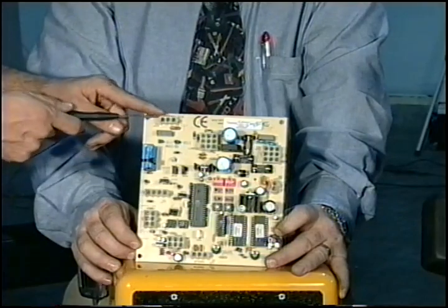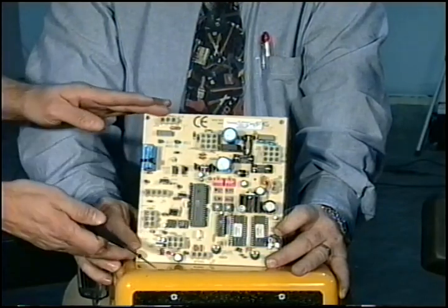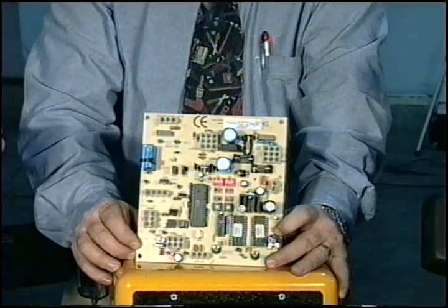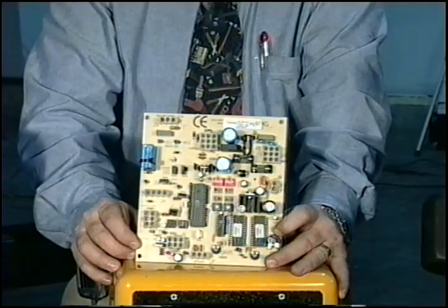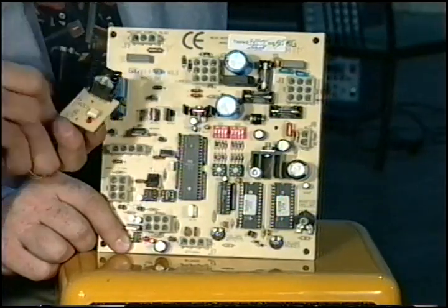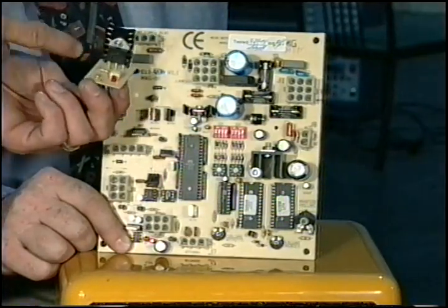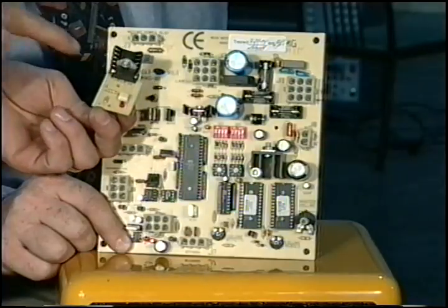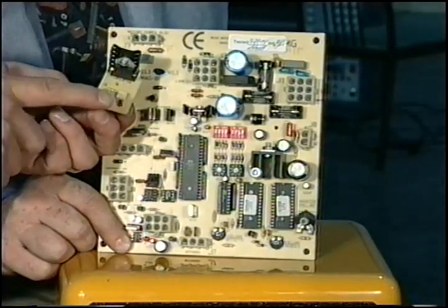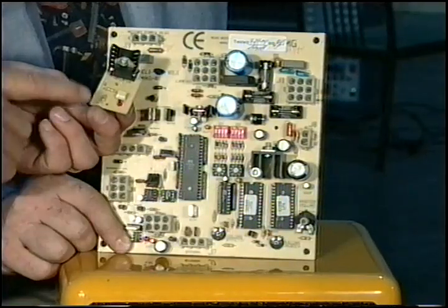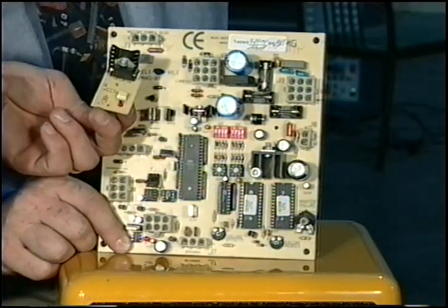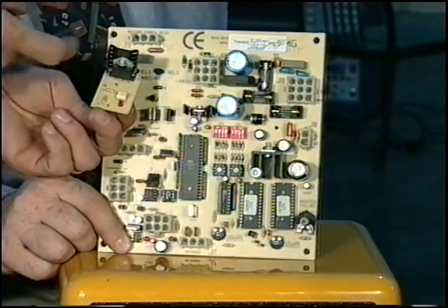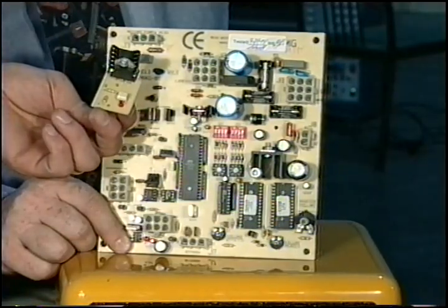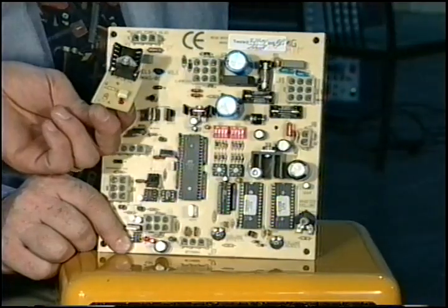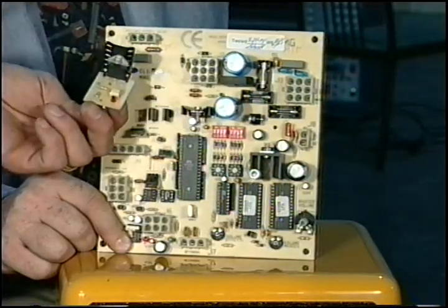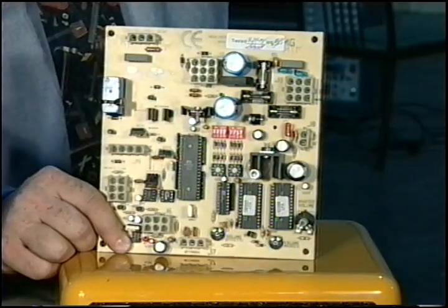The third thing that will make it go up is you have to have 120 here. So those are the three things that you want to check if your ride's not going up each and every time. Okay, some rides may not have a relay circuit. They may have a solid state circuit that looks just like this. It'll be in replacement for the relay, and it works exactly the same way. Whenever the circuit's activated, the red LED will light up, and then the transistor turns on and sends 120 to your pump. So if you don't have a relay and you have this, it's the same thing.